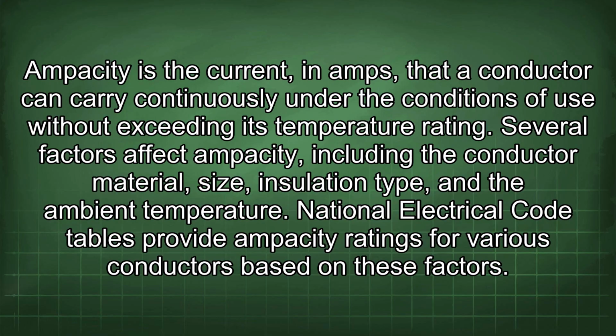Ampacity is the current, in amps, that a conductor can carry continuously under the conditions of use without exceeding its temperature rating. Several factors affect ampacity, including the conductor material, size, insulation type, and the ambient temperature. National Electrical Code tables provide ampacity ratings for various conductors based on these factors.